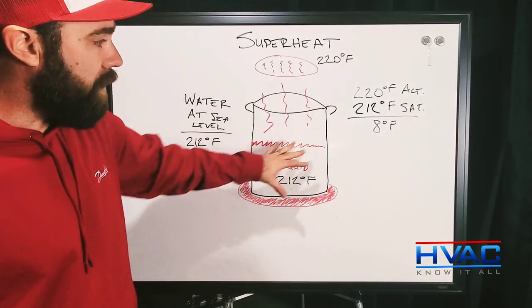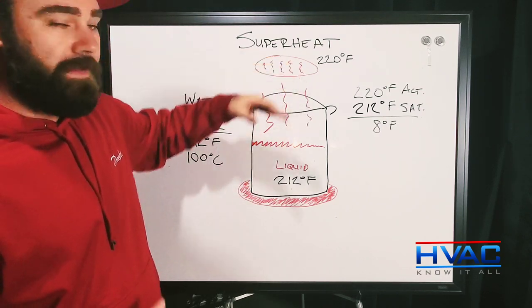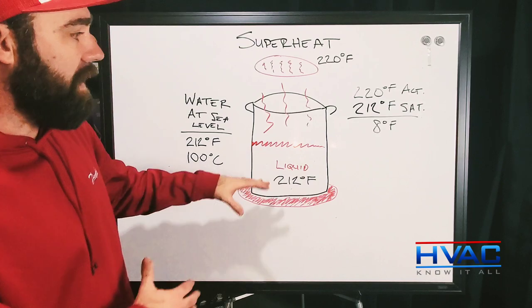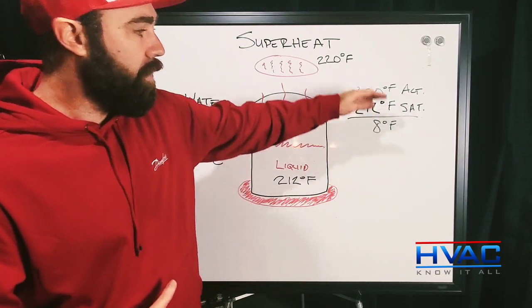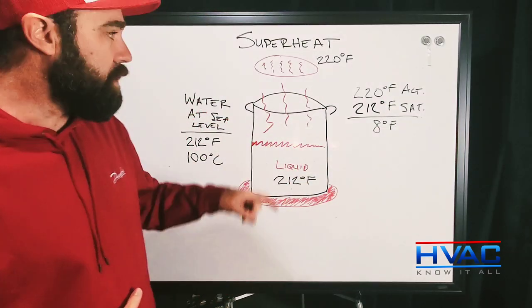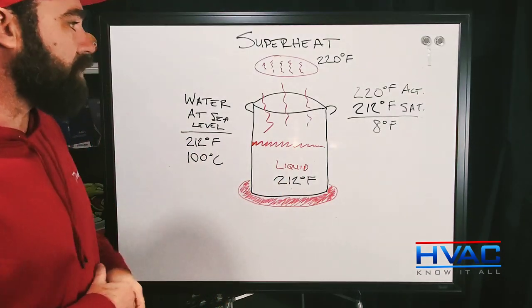So this example with water, I think, is going to help you with that. Just remember, vapor that's superheated is going to be higher than the saturation point. Whatever the difference is between the actual and the saturation point is going to be your superheat when we're talking about water. And that relates to refrigerant in the exact same way.